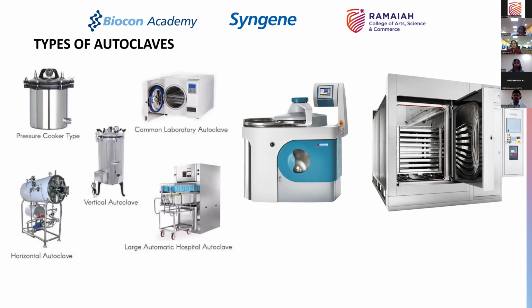They're going to be in the region of 600 liters or 300 liters, and they sometimes are sufficient to meet your requirement. There are microbiology labs where you need larger autoclaves, and obviously there you would use a vacuum displacement. So it is dependent on the quantum of load, the size of the autoclave, the type of the autoclave, etc., where you define which suits your purpose the best, and therefore you decide which autoclave you will buy.